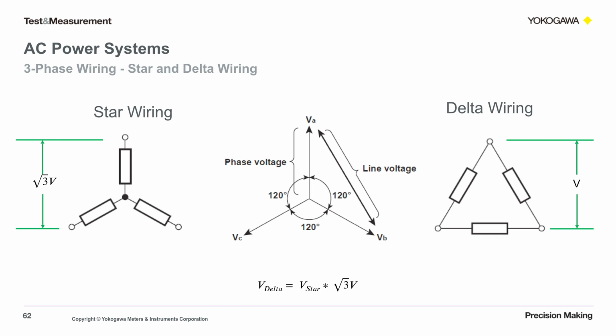The Yokogawa power analyzers have a delta-star transformation function that uses data from a delta connection, which you can use to compute to a Y connection, or line-to-line versus line-to-neutral. This solution does not require any additional hardware, false neutral, or floating of voltmeters.